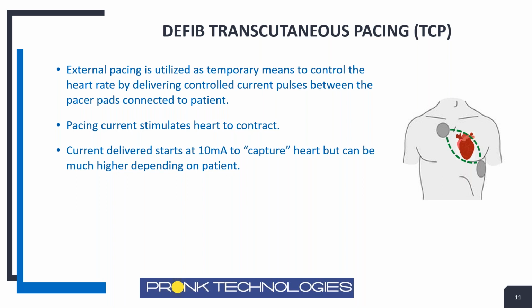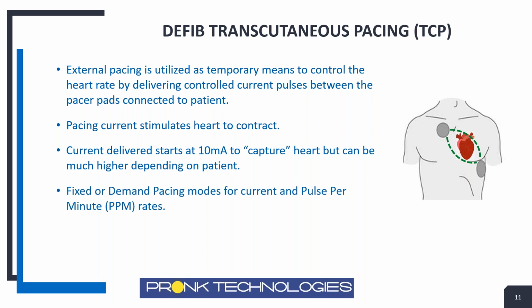Generally it starts at around 10 milliamps to try to capture a heart, but the patient could require much higher current. That's why we need to make sure we test at various current levels, so that we're sure the defibrillator captures across wide ranges, because it may not always be done at a particular set current. Testing at various currents can be very helpful. Defibrillators have fixed or demand pacing modes where you can set whether you want to always have current running through the heart at a fixed current value, or do it on demand, so that if the heart rate drops below a certain value, you go ahead and pace at that point.